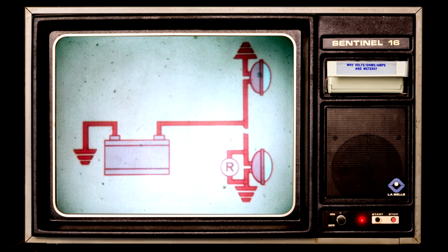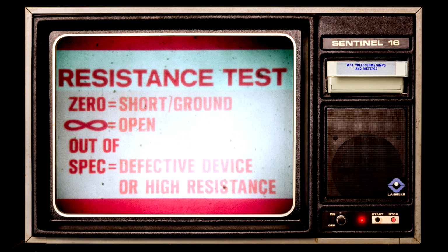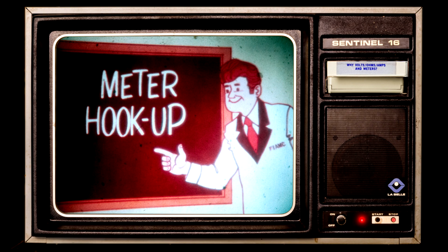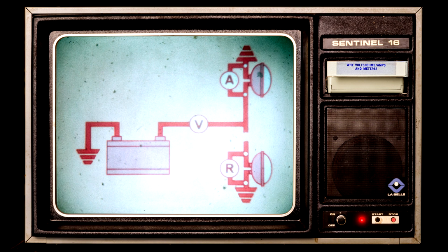The ohmmeter can only be connected across a circuit or device with the power removed. This meter has its own battery and will be damaged if connected to a circuit that has power applied. A zero reading indicates a possible short or unintentional ground. An infinite reading, like a sideways 8 on the meter, says you have an open circuit. And a reading out of spec could mean the device is defective or you have a high resistance loose connection. Again, let's stop for a moment and make sure we all know how these meters are hooked up and what they can tell you. Which 2 meters in this circuit are connected wrong?